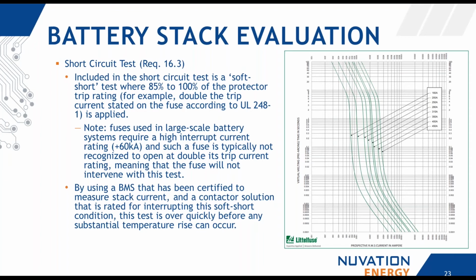As part of the short circuit test, if we were using a fuse that was 400 amp as its rating, double that would be 800. The pre-arcing time is off the graph for how long that would take to open. And during that time, you're having all sorts of components experience significant heating. But by using a BMS that is certified for measuring stack current and using contactors that are rated for the application, this test is over within seconds. So there's no substantial temperature rise. It's just a very trivial test. They set up, they do it, and it's done, and you move on to the next test. But without that recognition and without those contactors, it can be difficult to pass this type of soft short current test.